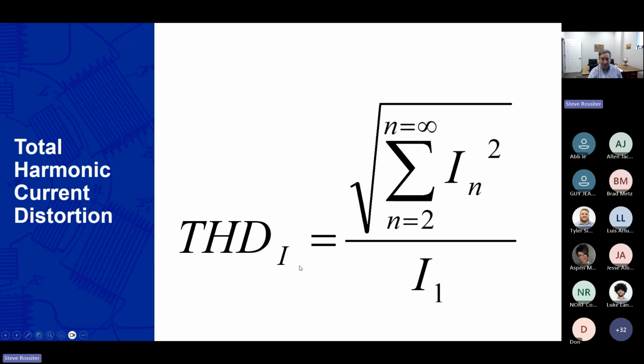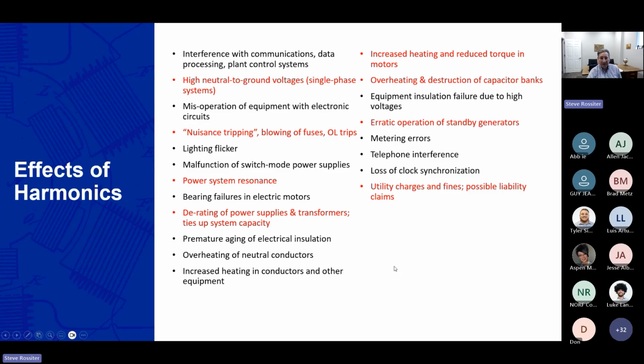If we take a waveform today in any one of your facilities, we would then take a meter or monitor that does power quality analysis. We'd see a certain amount of, let's say that we've got 30% harmonic distortion, current harmonic distortion. We would then do a fast Fourier transform and get it back into all those levels of frequencies to be able to know how to solve that. But at the end of the day, with too much harmonic distortion, problems are going to be caused both in the plant and at the utility level. And these are a few of those that we recognize easily.